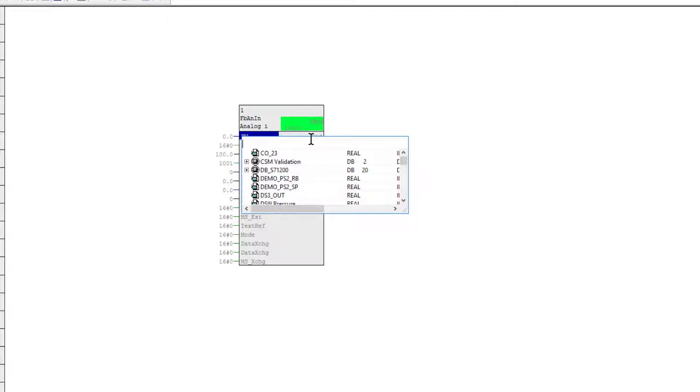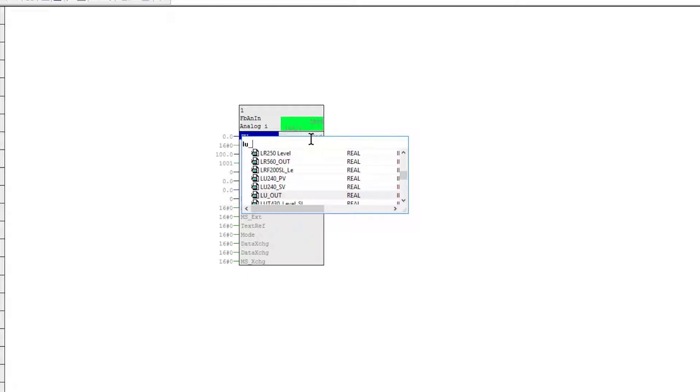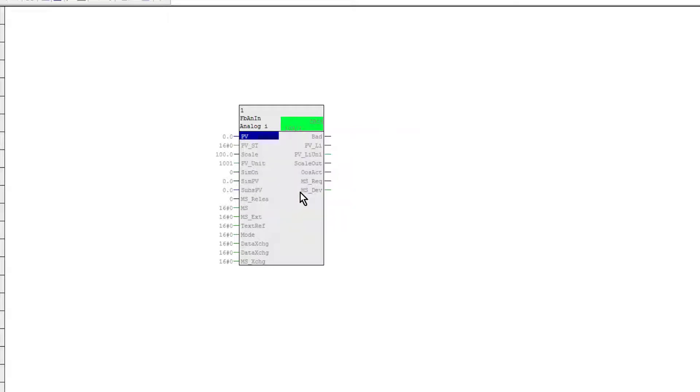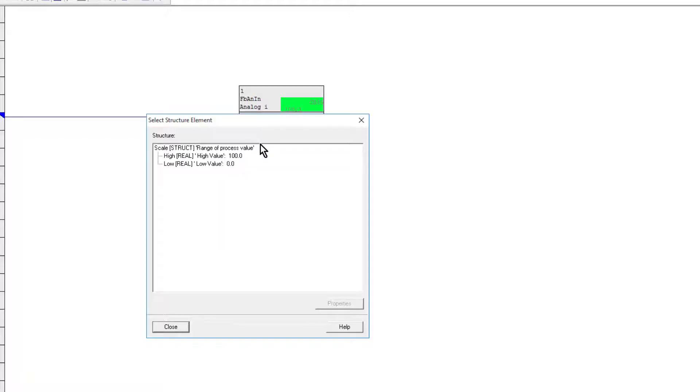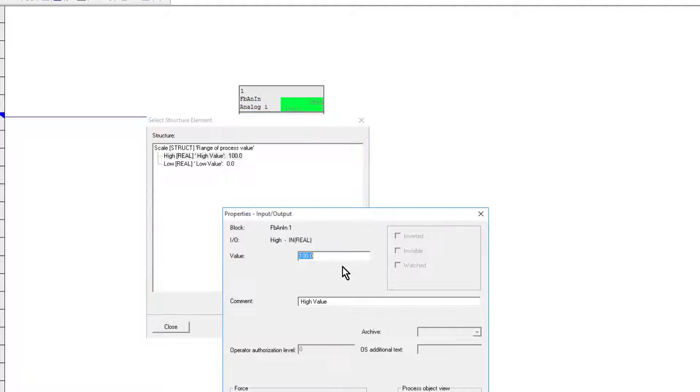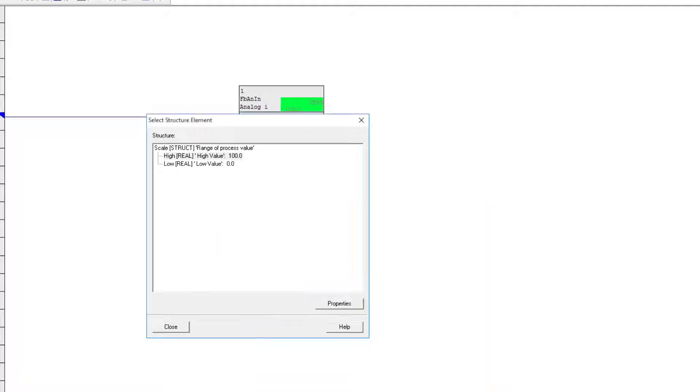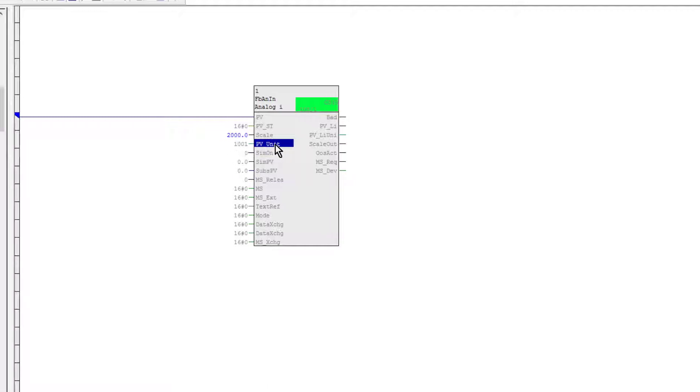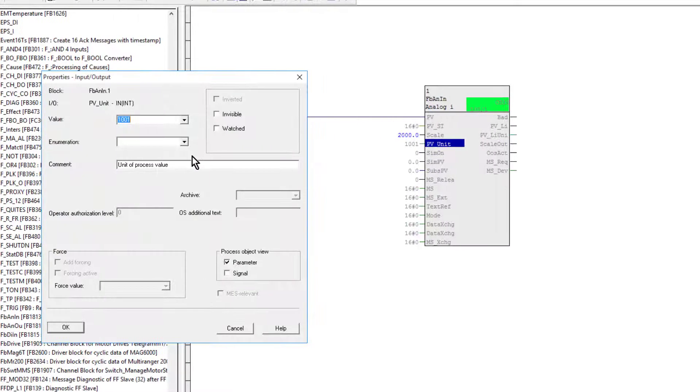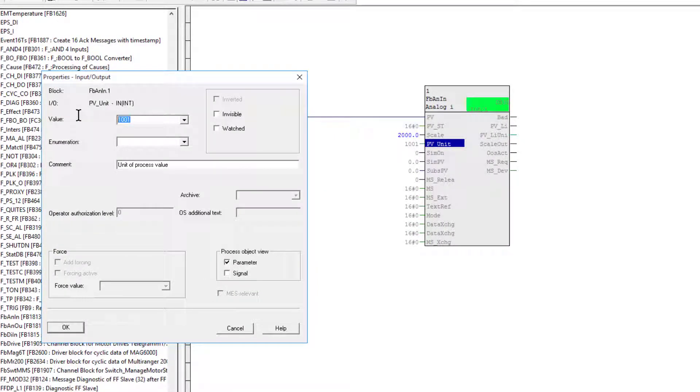I think we called it LU out, I can see it there. And then the only other thing I need to do is manually set the scale. It was 2000 litres, and then you have to put your units in this parameter here. In this particular example, we're going to set that to what it was before.